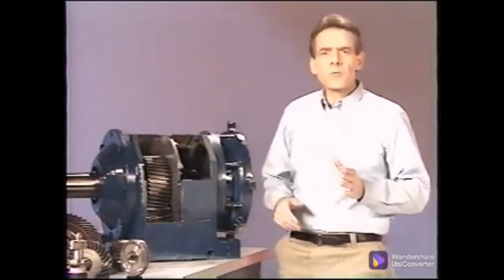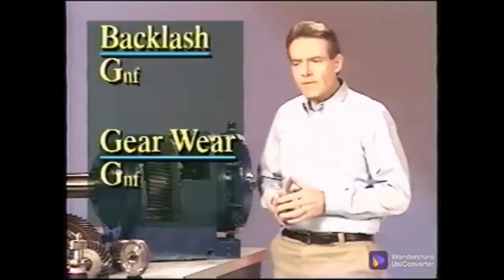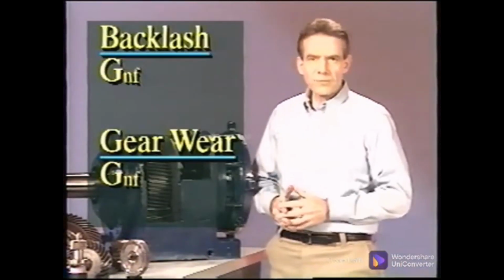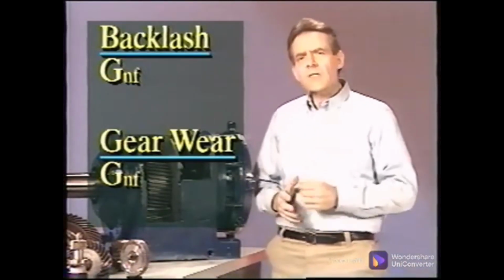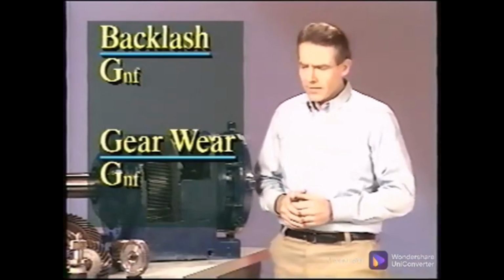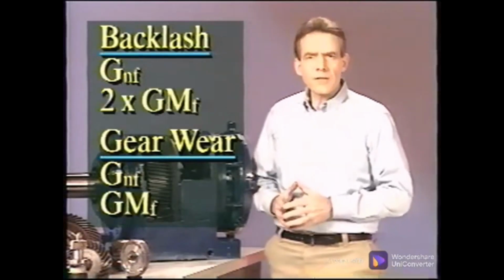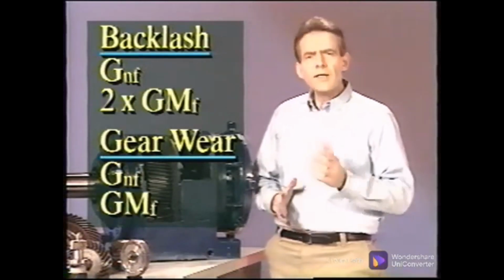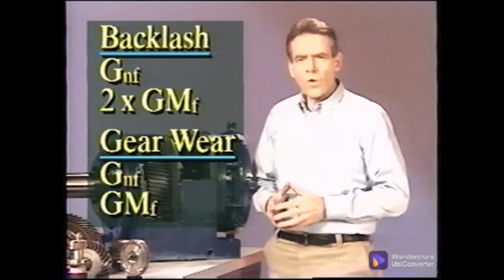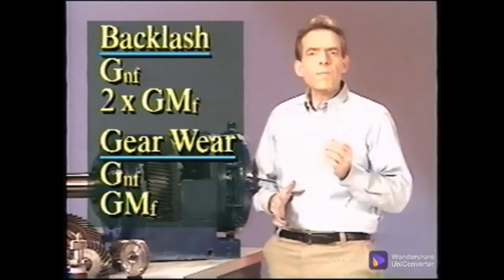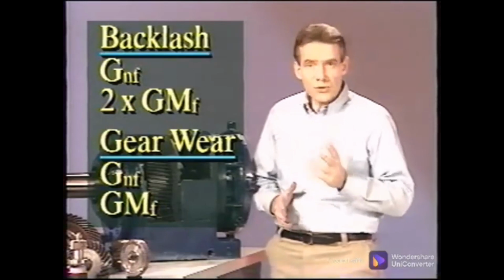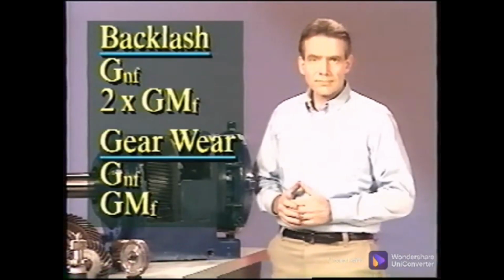The backlash and gear wear data are similar in the fact that they both excite the gear natural frequency, and it may have sidebands of shaft speed. The two differ, though, in the dominant gear mesh frequencies. Gear wear tends to have a dominant 1 times gear mesh, while backlash tends to have a dominant 2 times gear mesh frequency.